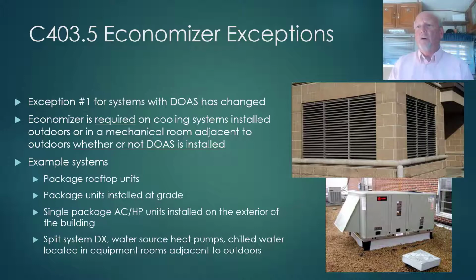Economizer is now required on all cooling systems installed outdoors or in mechanical rooms adjacent to outdoors, whether or not DOAS is installed. So if you have an occupancy type that requires DOAS and you're using packaged rooftop units, economizer is required on those units. If you have a DOAS system and you're using package units installed at grade, economizer is required. If you've got DOAS and you're using single package vertical AC heat pump units, as we talked about earlier on portable classrooms, economizer is required. And if you're installing split system DX cooling, water source heat pumps, or chilled water fan coils located in equipment rooms adjacent to outdoors, an economizer is required. So this significantly expands the economizer requirements even when you're using DOAS.